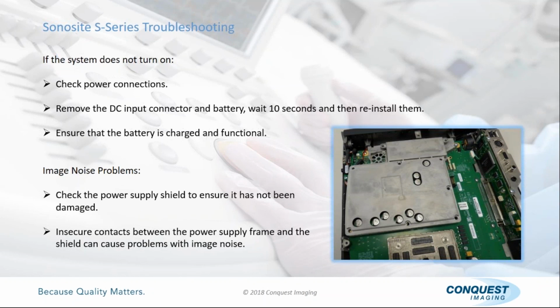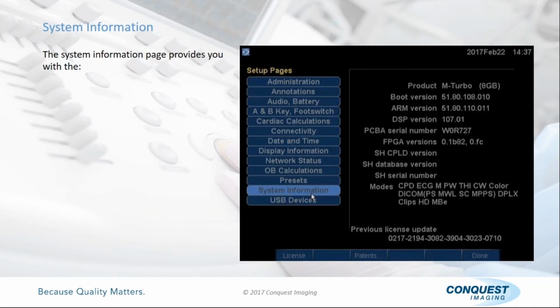And one of the things that they do have in the S-Series is this cover. This is a shield. And if that cover isn't mounted correctly, or gets dirty, or gets a carbon deposit between it and where it's mounted to, it can induce noise to your image. So this is one of the things that they ask you to check if you're having an image artifact or noise problem. And it tells you some of the system information here.